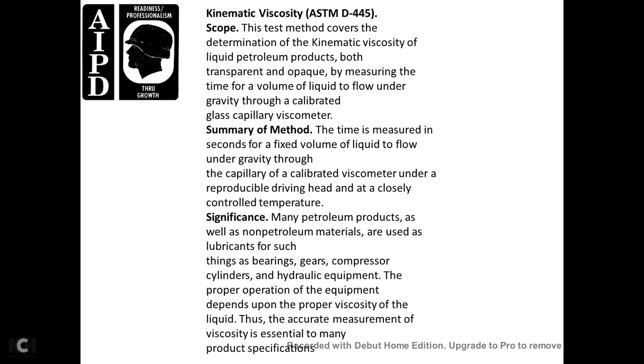Kinematic Viscosity — ASTM D445. Scope: covers determination of kinematic viscosity of liquid petroleum products by measuring the time required for a volume of liquid to flow under gravity through a calibrated glass capillary viscometer. Times are measured in seconds for a fixed volume of liquid to flow through the calibrated viscometer under a reproducible driving head at a closely controlled temperature.